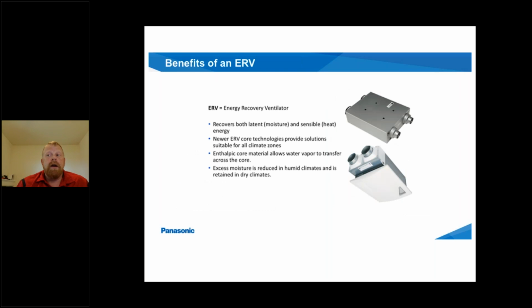Like I say, benefits of the ERV. The ERV will recover both latent and sensible heat. So it will recover actual temperature, and it will recover relative humidity and pass that through, so that the house will get what it needs. Excess moisture can be reduced in a humid climate, but in a dry climate, it can retain moisture. So it's a perfect mix for that air exchange.